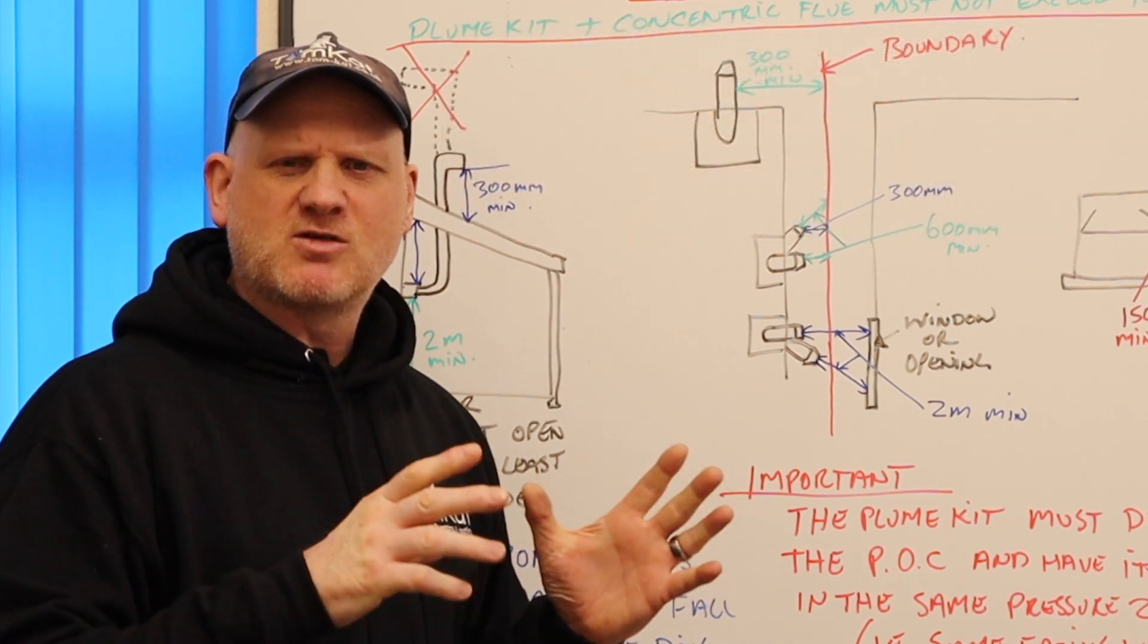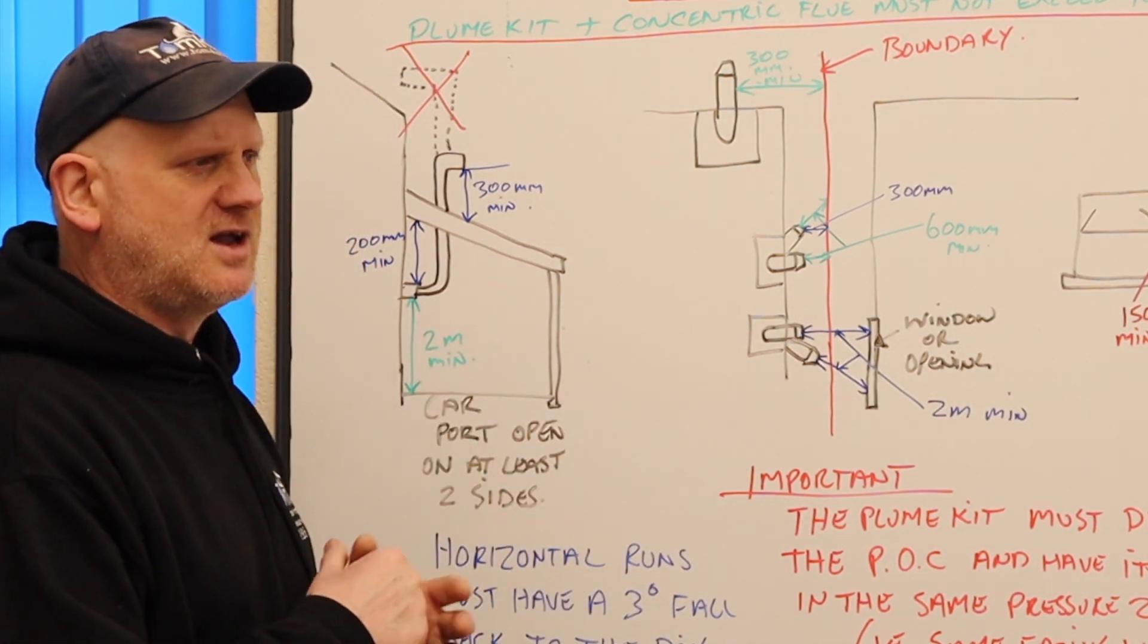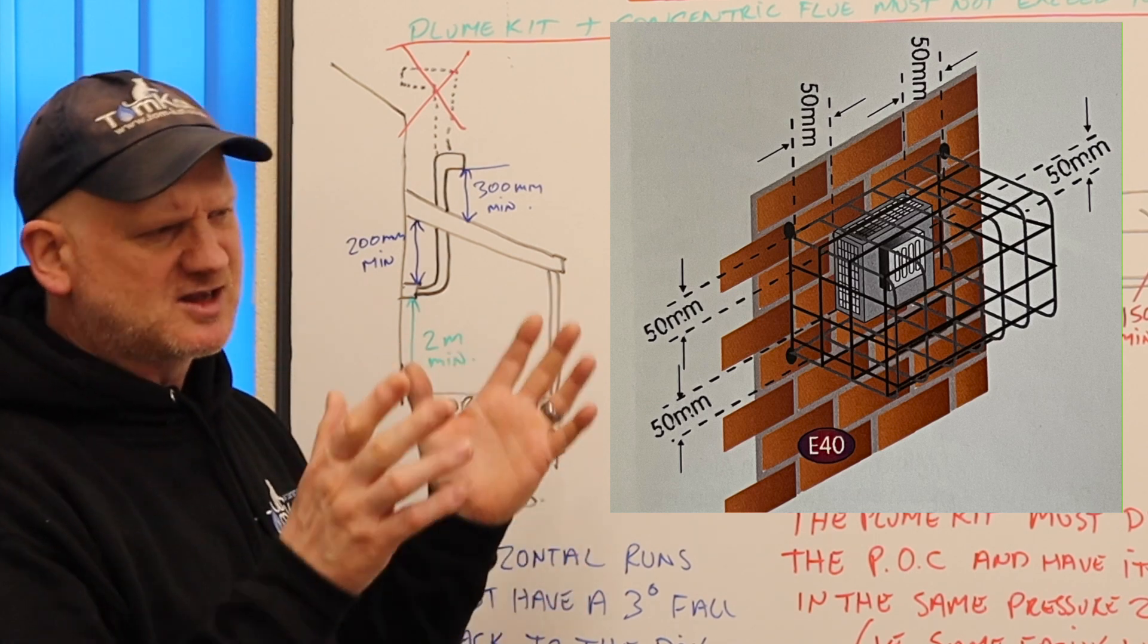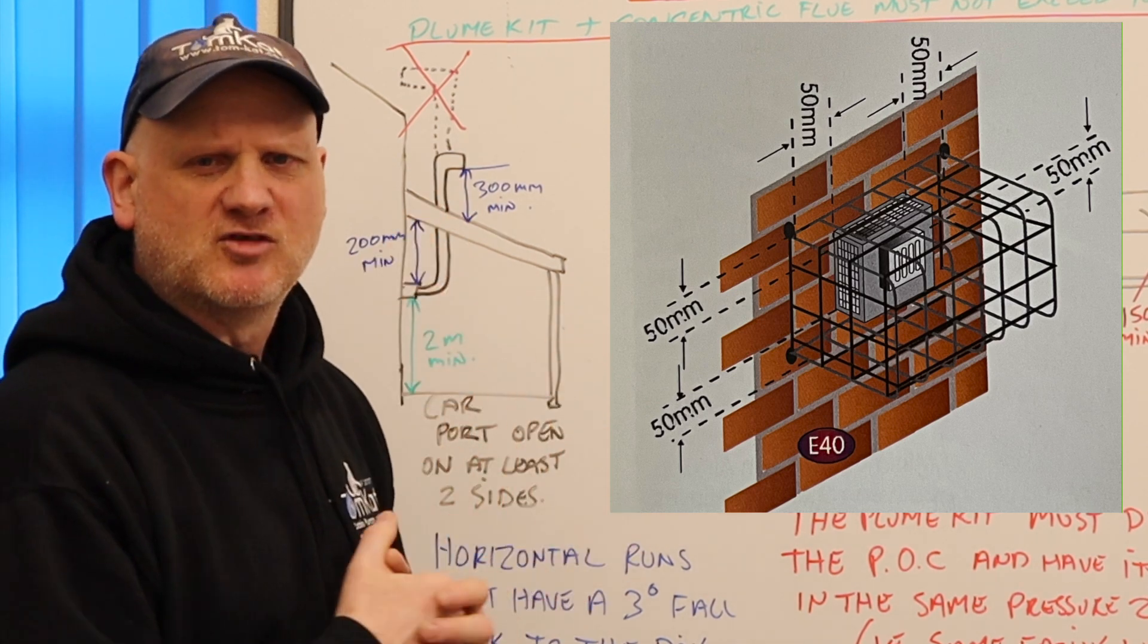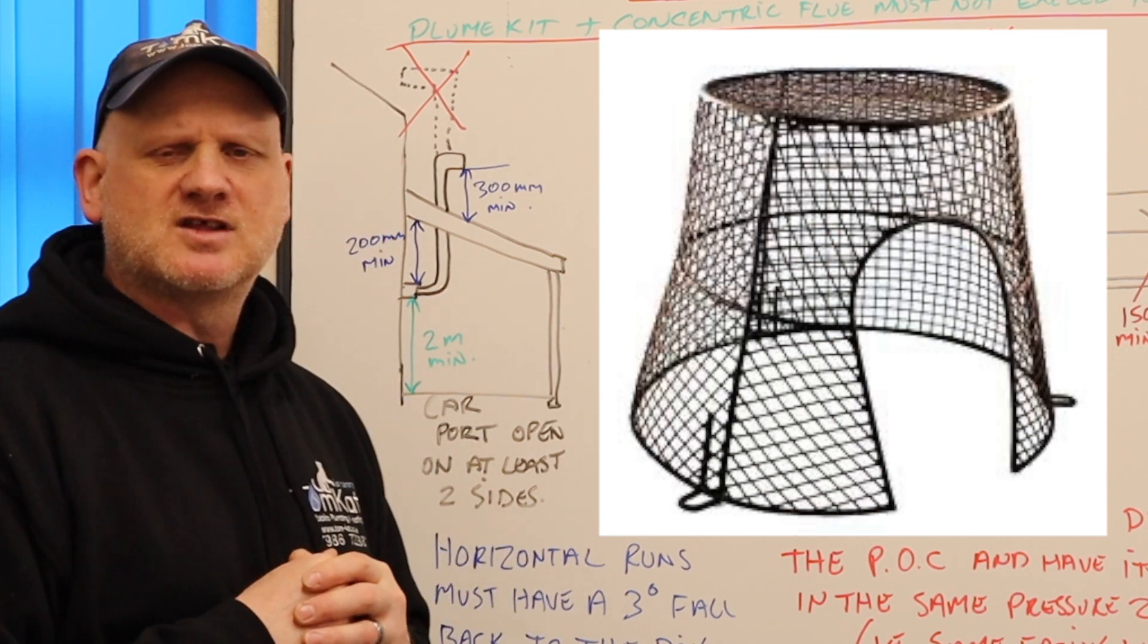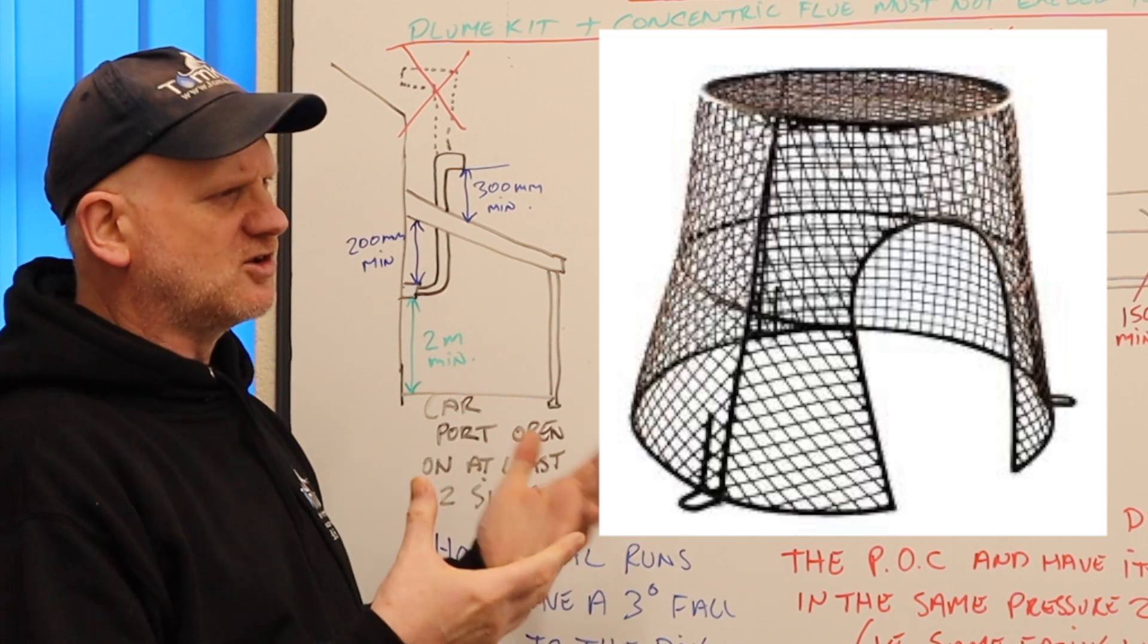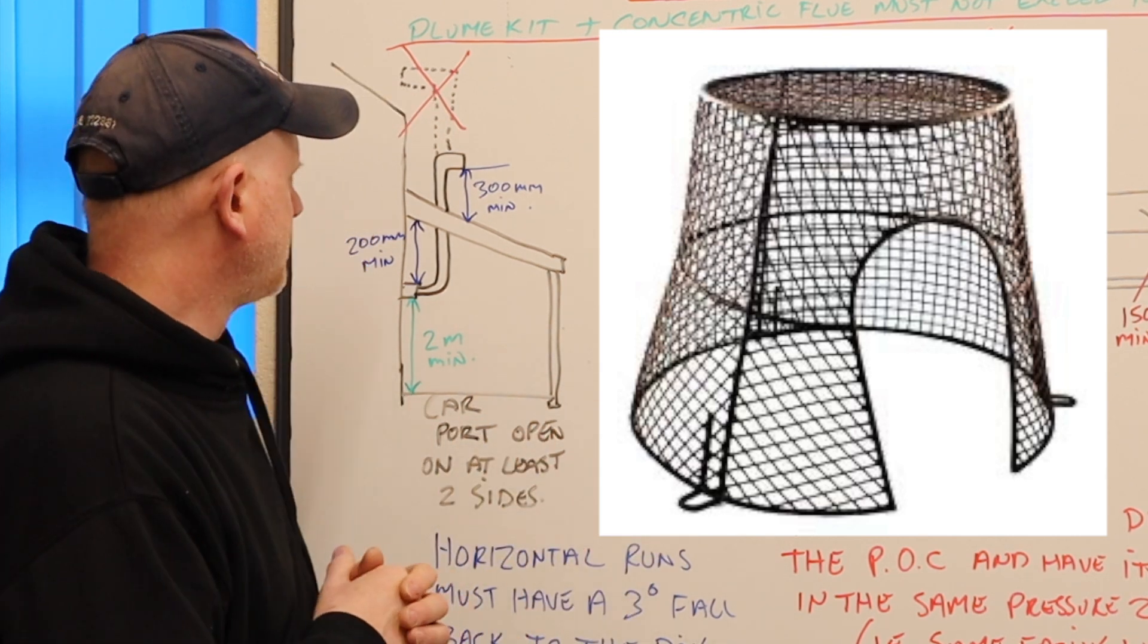But it's now there just to protect the flue system rather than us getting burned from it. But we still need to comply. It still needs to be 50 mil all the way around from the front. And we can get specialist terminal guards for this flue system. They're normally coated or they're made of stainless steel or they're plastic coated.